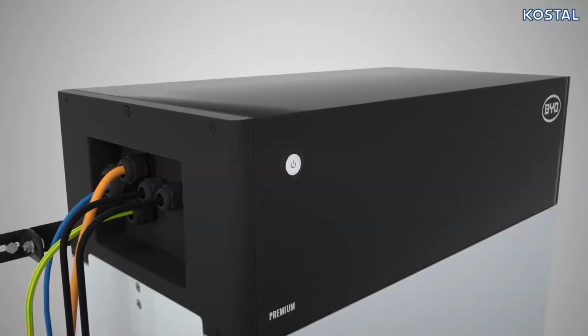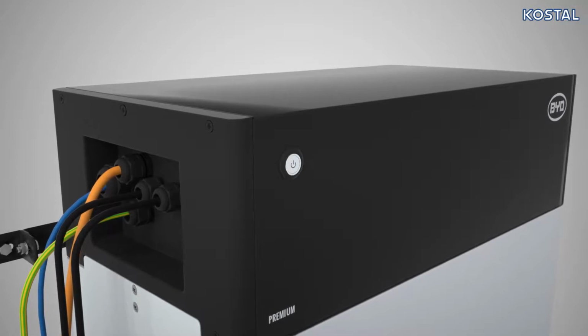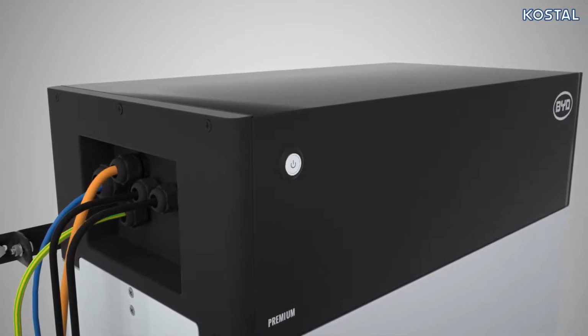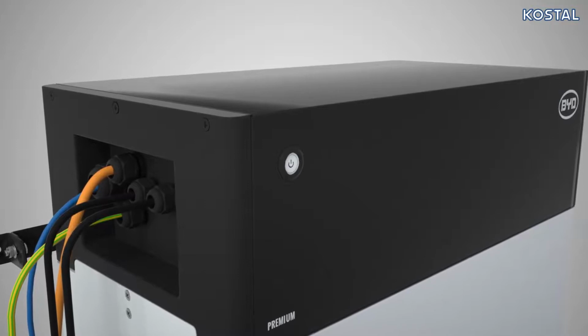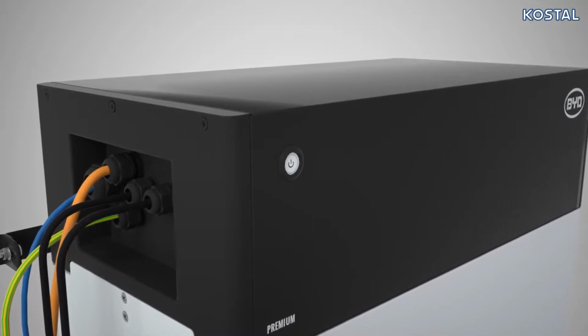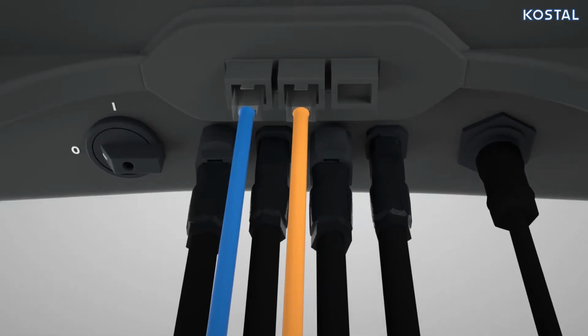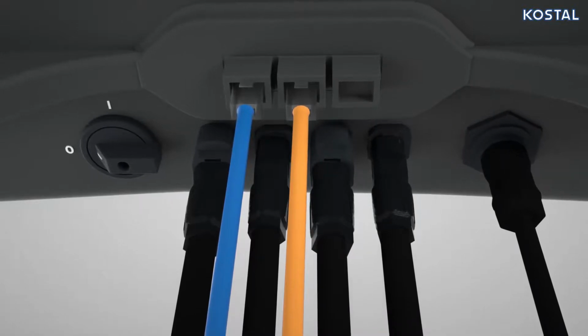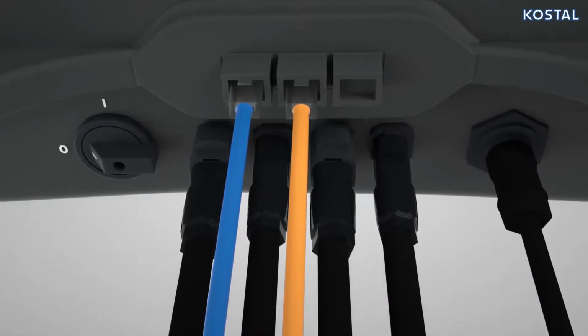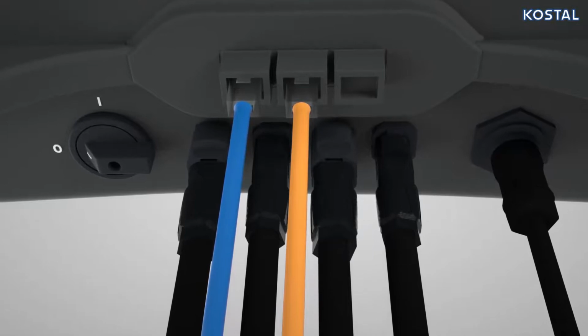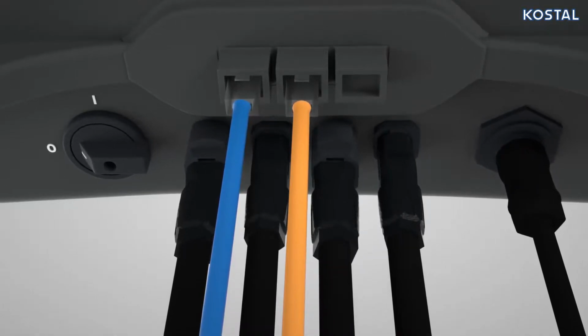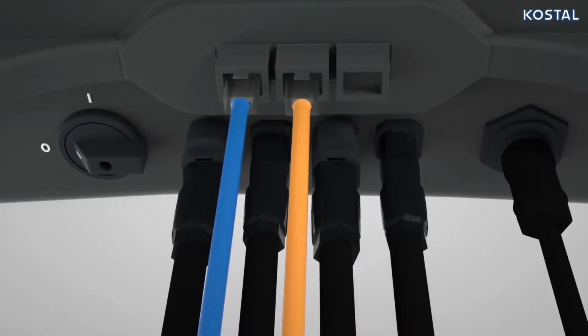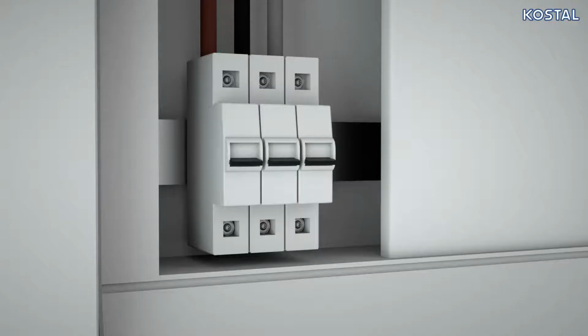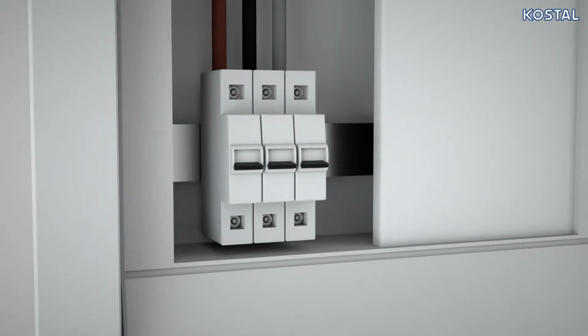Start by switching off the battery system by pressing the power button on the front for at least 6 seconds. The DC connections in the PIKO MP Plus are configured as PV inputs as standard. This means that the DC input needs to be changed to battery operation. To do this, first switch the AC supply off again.